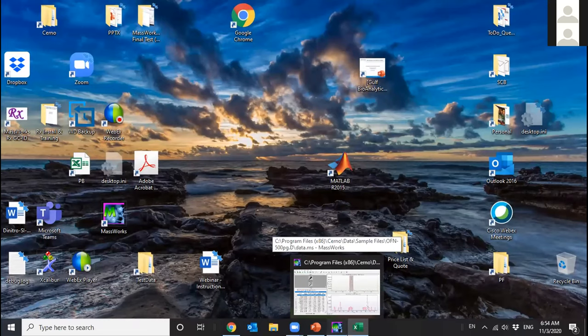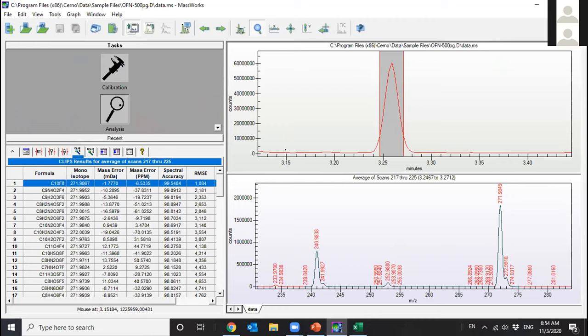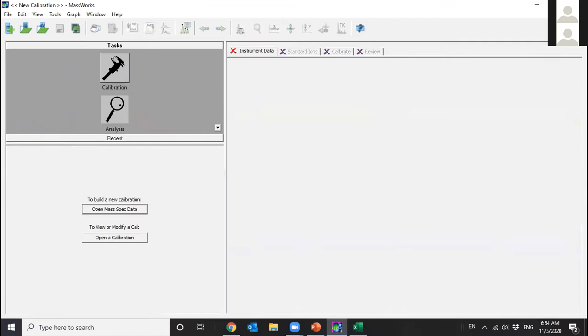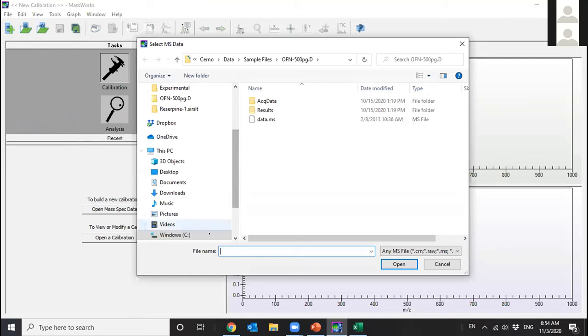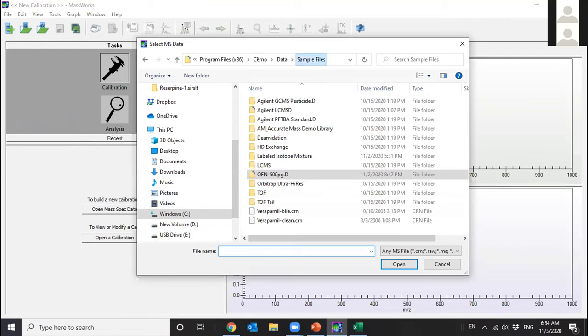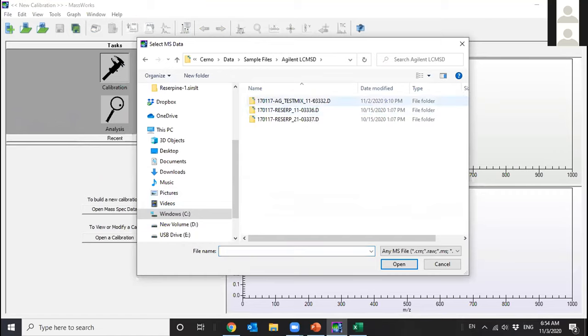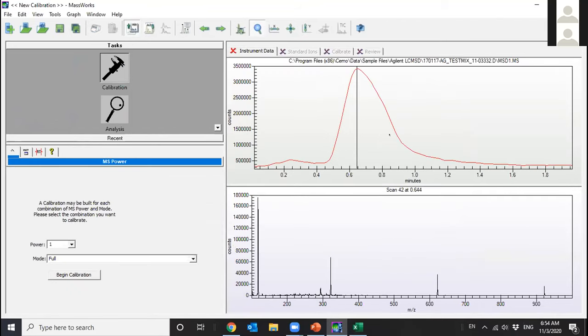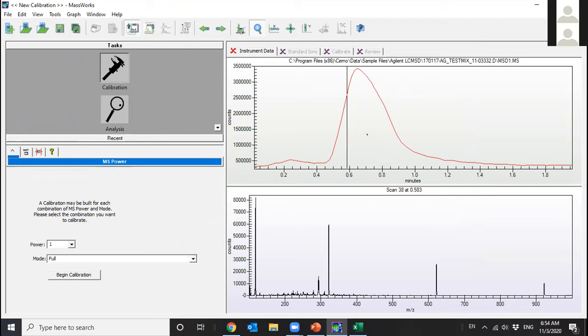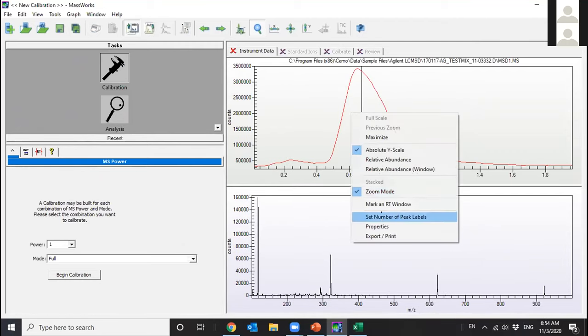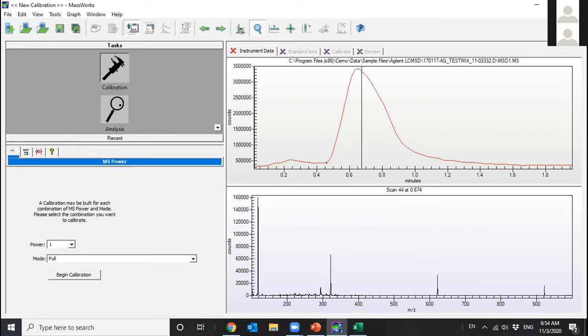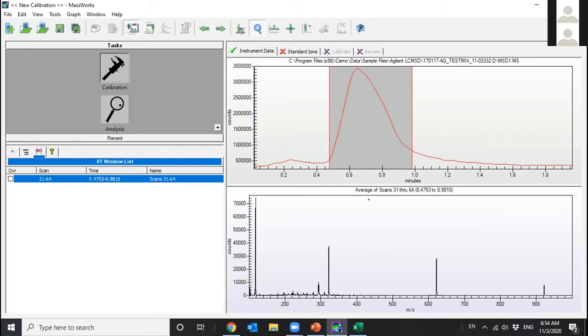So with that, I will switch gears to show you the LC-MSD. For LC-MSD, we still have to do a manual calibration by hand. So you would click the calibration button under the task, and then we would go open mass spec data to do the manual calibration with. Here we have LC-MSD data that's already acquired using the loop injection of the Agilent tune solution in a 2 minute run. You can see that's where the tune compound comes off, and you can follow the quick guide to mark the RT window. We get the average mass spec to do the calibration with.